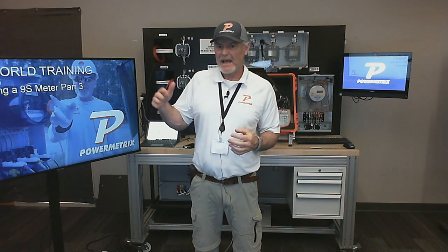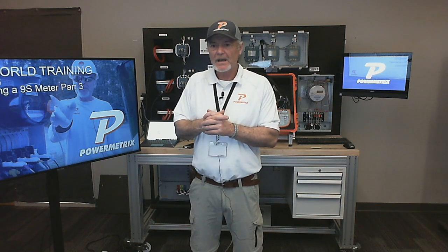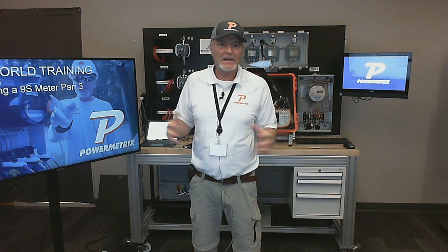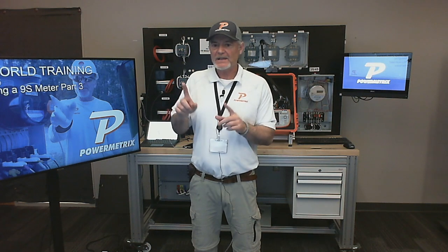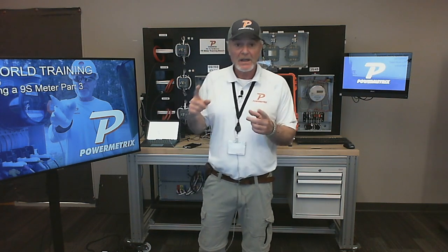It looked like our secondary current was up though, around 2 amps, which means we should be able to test it pretty easily. When you get low secondary current, it's tough to test those CTs. Once you start seeing less than half an amp, it's going to be tough to test them. We didn't see anything crazy on the vectors so far, no polarity reversal or cross phasing, nothing that really jumped out at us. We also didn't see any one of them being way less than the others, which could be indicative of problems lengthwise on the vectors.